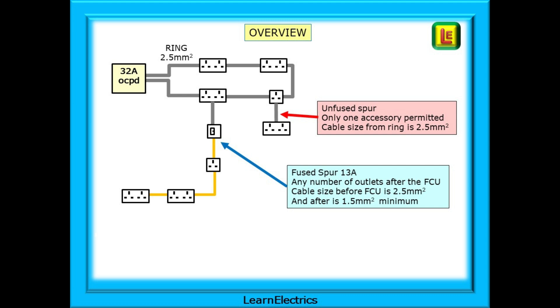Let's have a quick overview of what we've done so far in this video. In our example, a 30 or 32 amp ring circuit should be wired in 2.5 by 1.5 twin and earth. From each accessory that is actually on the ring, we can take an unfused spur to one spurred accessory and one only. The cable size from the ring to the spurred accessory must be the same size as the cables forming the ring, in other words 2.5mm. If we use a fused connection unit, a fused spur at 13 amps, then we can have as many accessories as we need after the FCU. The cable from the ring to the FCU must be 2.5mm, and after the FCU we can, if we wish, reduce the cable size to 1.5mm.